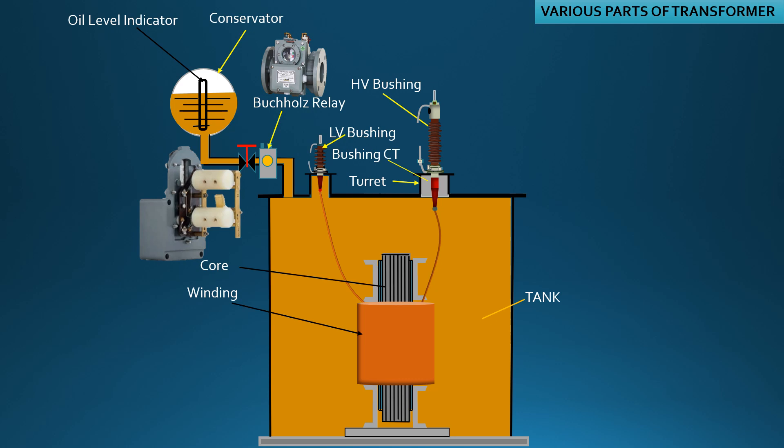Sufficient gas accumulation tilts one of the floats of the Buchholz relay that initiates an alarm, and then tilts the second float to issue a trip of both side circuit breakers of the transformer when accumulation of gas is more.